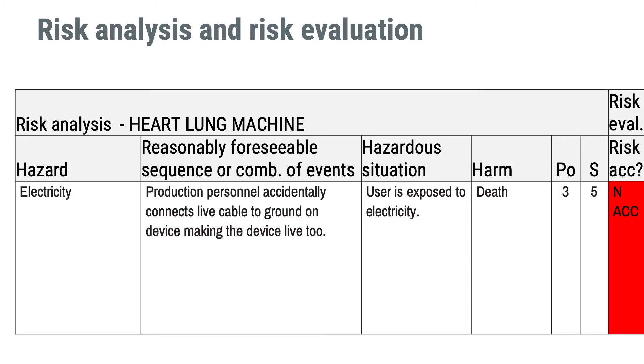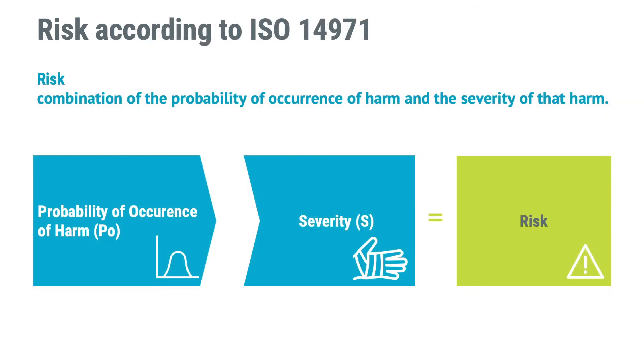Based on the hazard in this example, we came up with a sequence of events where a person in production by mistake connects a live cable to ground, which makes the whole device casing live. The user is exposed to electricity, which in some cases could kill you — not every time, I admit, but it could kill you. So we write up death as the harm in this example. The next step is to estimate the risk.